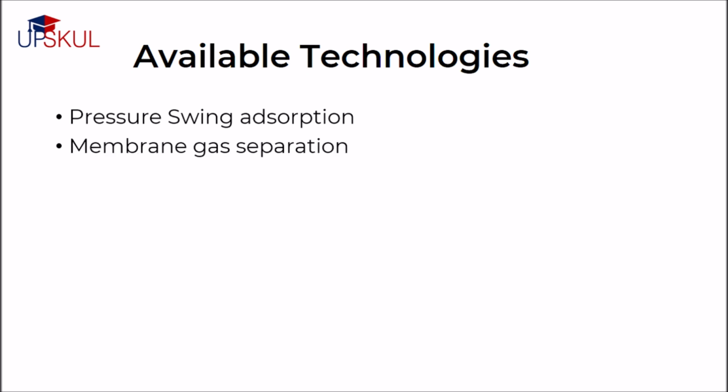In the case of oxygen concentrators, there are two widely used technologies: pressure swing adsorption, where specific adsorbent materials like zeolites, activated carbon, and molecular sieves are used as a trap, adsorbing the target gas species at a high pressure, and membrane gas separation, where gas mixtures can be effectively separated by synthetic membranes made from polymers such as polyamide or cellulose acetate, or from ceramic materials.